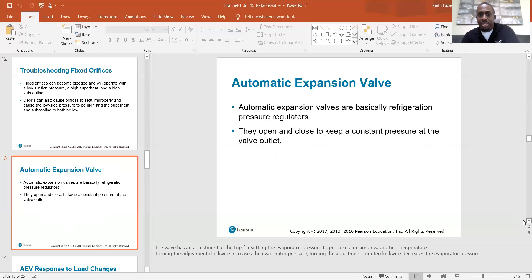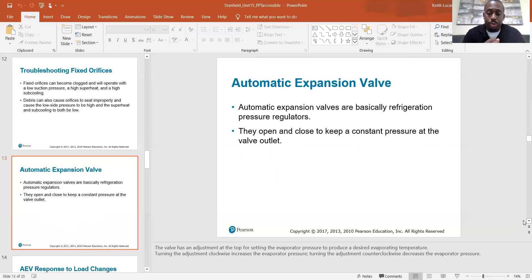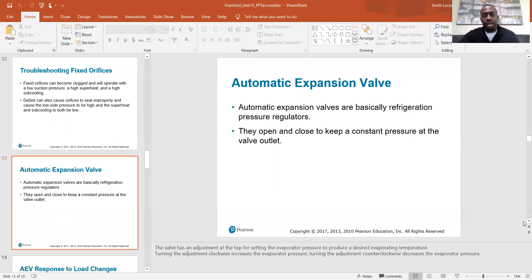Automatic expansion valves are basically refrigeration pressure regulators — they open and close to keep a constant pressure at the valve outlet. The valve has an adjustment at the top for setting the evaporator pressure to produce the desired evaporator temperature. Turning the adjustment clockwise increases the evaporator pressure; counterclockwise decreases it. But don't just start turning adjustments before ruling out other issues — like dirty coils or dirty filters — that could be causing your pressure readings to be off. Make sure all your fans are turning and the system is functioning correctly before adjusting the metering device.